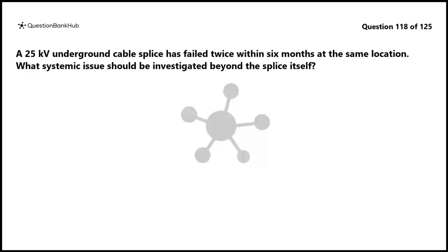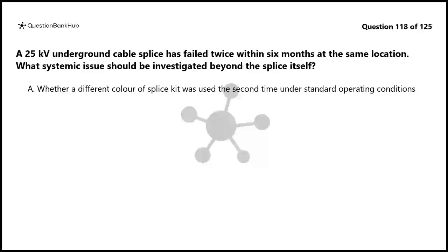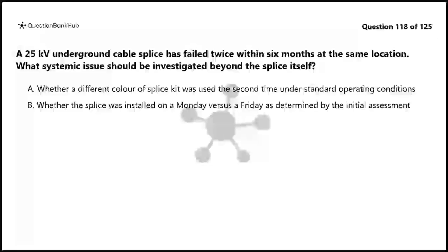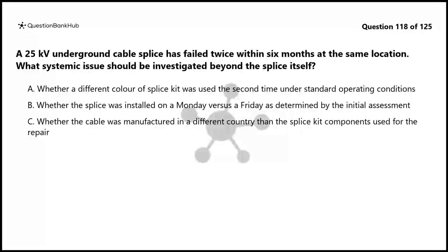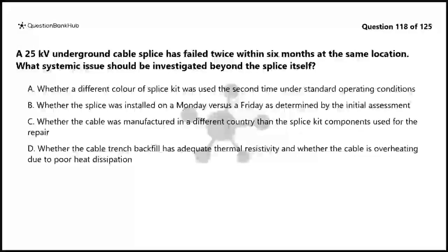Question 118. A 25 kV underground cable splice has failed twice within 6 months at the same location. What systemic issue should be investigated beyond the splice itself? A. Whether a different color of splice kit was used the second time under standard operating conditions. B. Whether the splice was installed on a Monday versus a Friday as determined by the initial assessment. C. Whether the cable was manufactured in a different country than the splice kit components used for the repair. D. Whether the cable trench backfill has adequate thermal resistivity and whether the cable is overheating due to poor heat dissipation.